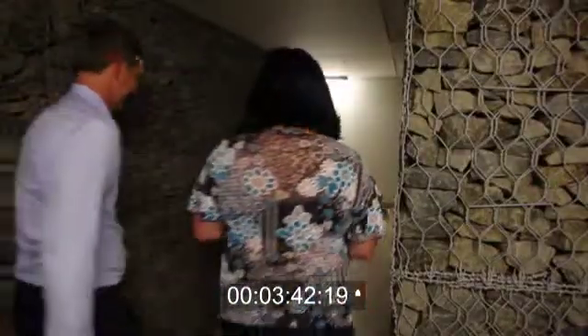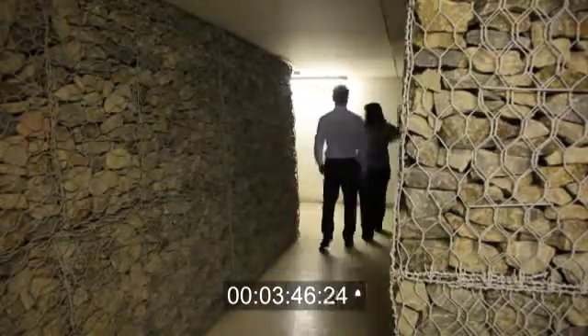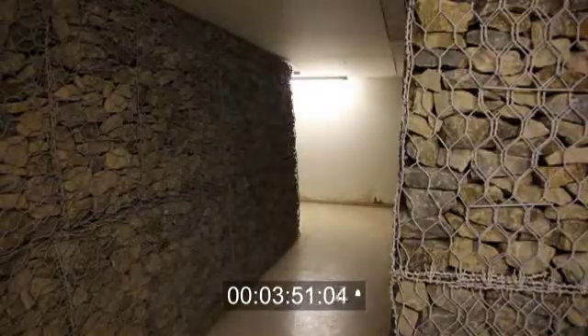And those rocks provide great thermal stability, and in summer they're much cooler than outside air. In winter they're warmer than outside air because you have to have a very high proportion of fresh air through your system. So it cools that outside air before it gets into the system. Massive energy savings via that sort of process. And then in winter, probably less dramatic in Perth because it doesn't get that cold, but even in winter in Perth it can get a bit chilly outside. These stones will have a slightly higher temperature.